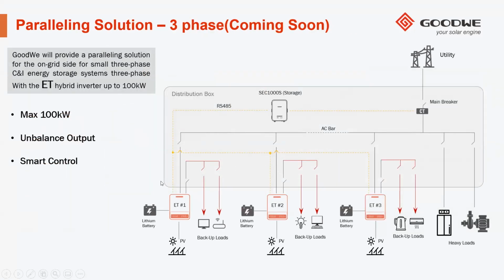Then for our 3-phase inverters, we've got paralleling coming as well, but only for the grid connected side. Unfortunately, the backup won't be able to parallel on these units at this point in time. This is good because you can go up to 100 kilowatts and have your unbalanced output to maximize savings from the utility. These can be used with or without batteries. It's got very intelligent battery control with the inverters. So if you do have batteries and you have different sized battery banks, it will interactively control the amount of discharge from the batteries to match the loads.